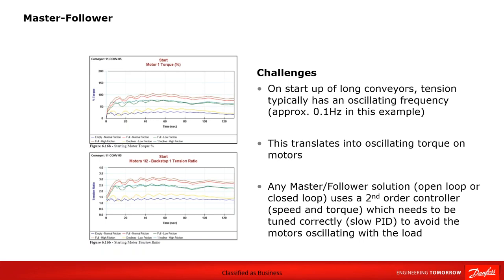So as I said previously, on startup of long conveyors, tension, we have to be very careful. We have to start up and ramp up slowly because the tension typically has an oscillating frequency. What we're showing here is approximately 0.1 hertz in this example. So this translates into an oscillating torque on the motors. So any master follower solution, open or closed loop, uses a second order controller. So in other words, speed and torque, which has to be tuned correctly. In other words, slow PID, because we want to avoid the motors oscillating with the load.